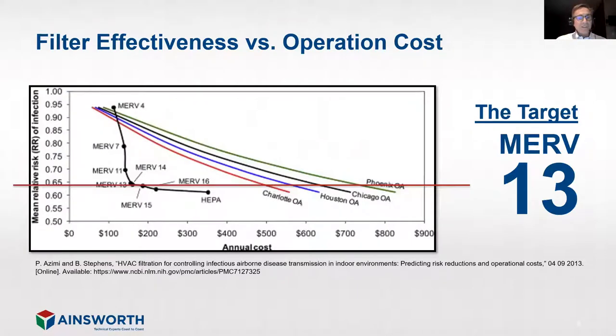This is a very nice study. I have the reference at the bottom if you want to take note of that, that shows that going above a MERV 13, you don't get much benefit and your cost of use just increases. There's a sharp turnaround at MERV 13, where the risk of infection stops reducing but the cost keeps going up. So that inflection point is really the point where you want to stop. So don't go installing a HEPA to catch those particles. It's not worth it. But going from a MERV 7 to a 13 reduces your risk by 15%.